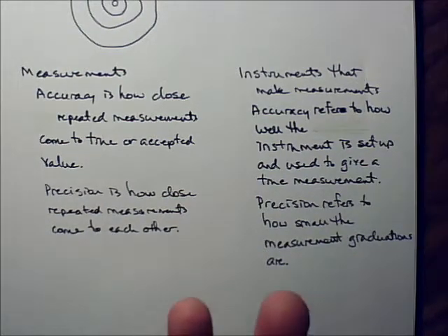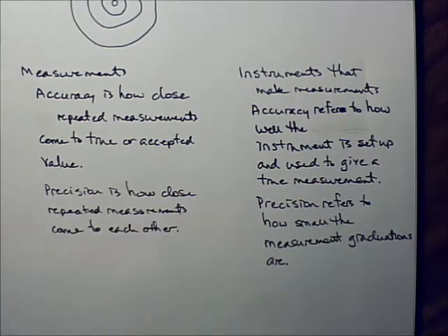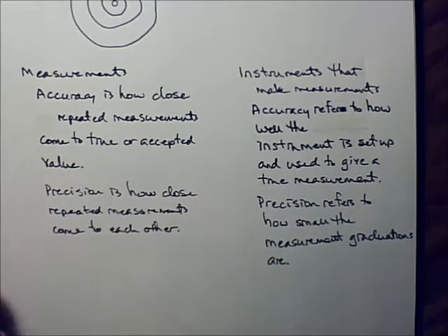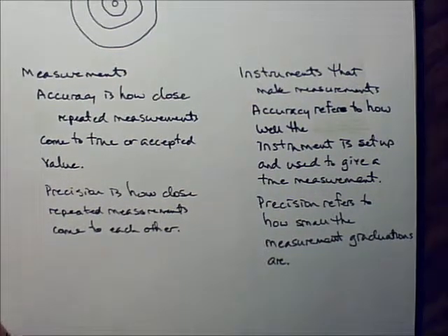So you are flexing the floor. Every time you take a step, you make that floor move. Now you don't feel it, it doesn't seem like it, but you're making that floor move. So when you step close to a really precise balance, that instrument will pick it up. And you can actually see the balance move. You can see the floor flex. Okay? Pretty cool, huh? All right. Any other questions?